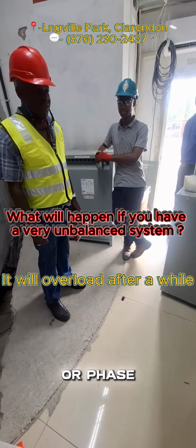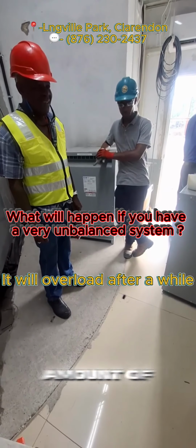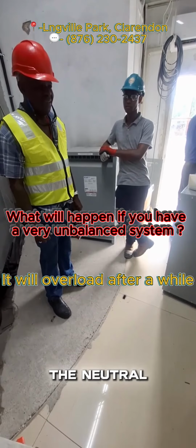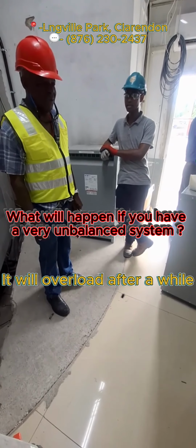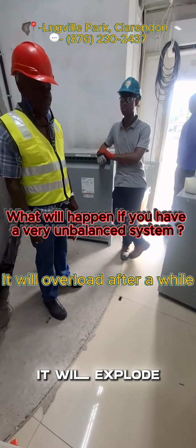That is exactly what happens when you have a poorly balanced three-phase system. When that amount of current goes back on the neutral, if the neutral isn't sized properly, or the transformer isn't sized properly, it will explode.